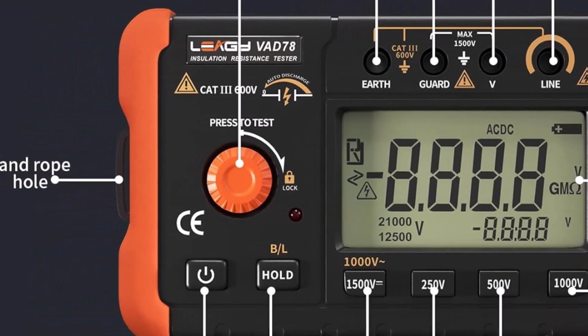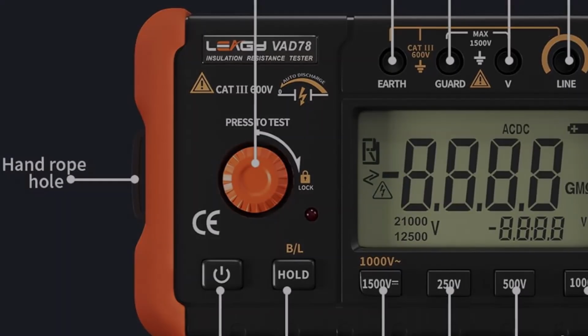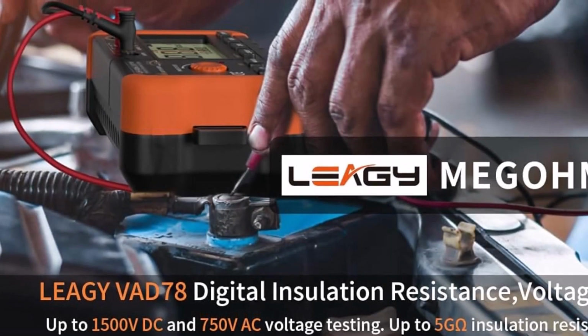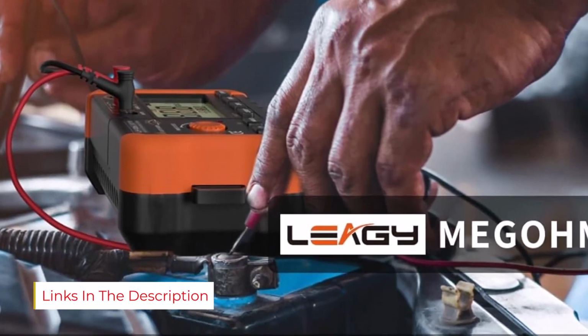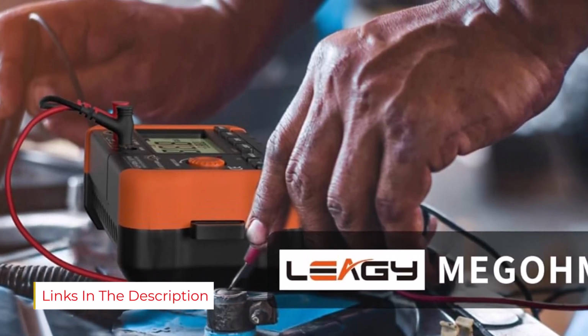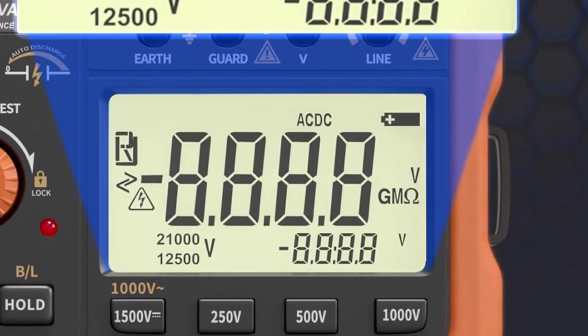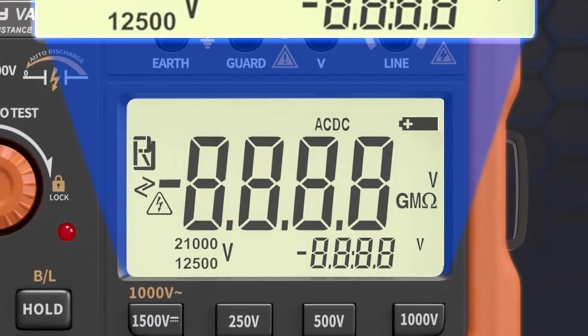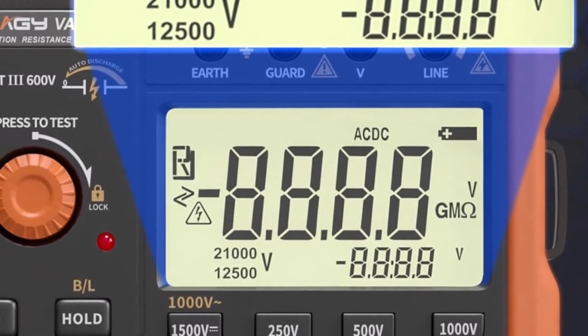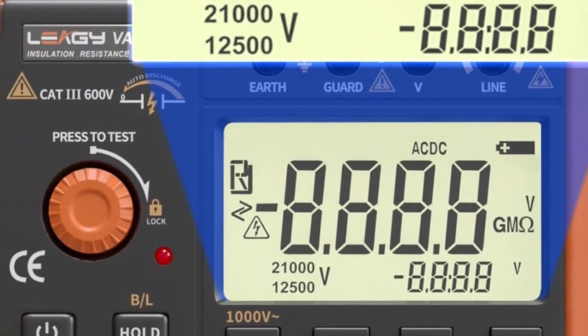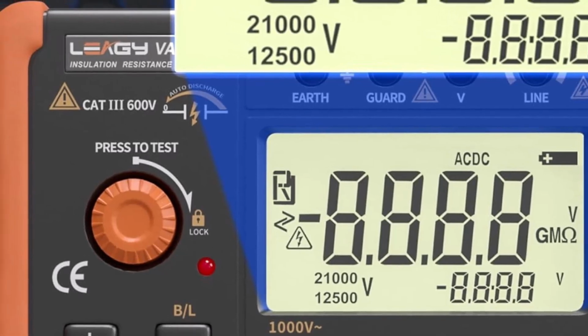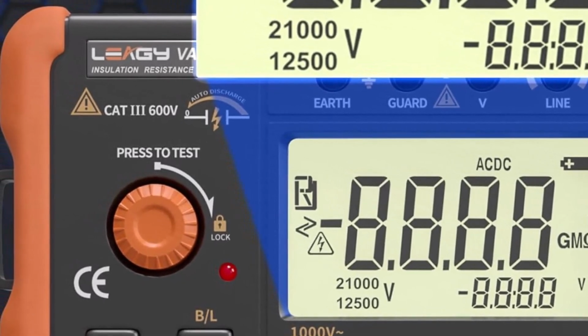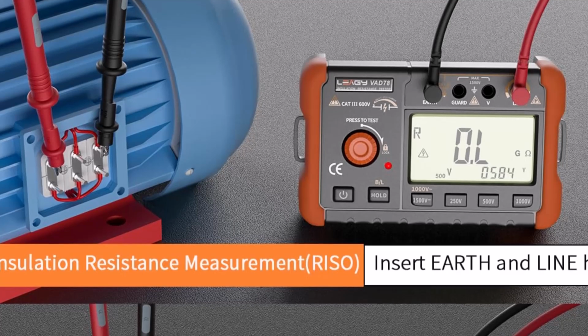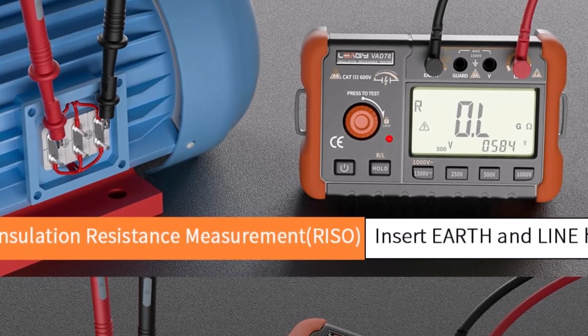Still, you will be able to measure up to 2000 megohms resistance on this resistance tester at 1000 volts. On top of that, this device also offers an accuracy of about plus or minus 4% plus 2 digits of the result, which is pretty good for such an affordable insulation tester. As for the display, you will find a large LCD display on the LEAGY Victor VC60B Plus with backlit features. Since this is a pretty compact device, you will notice minimal power consumption that is about 300 milliwatts.